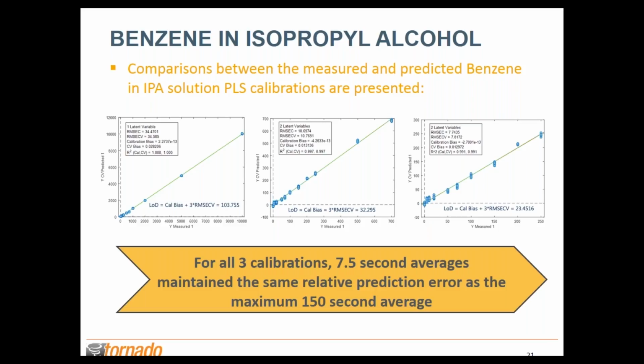Doing so, the full range calibration had an average predictive error of 35 ppm, with the order of magnitude of the limit of detection of around 104 ppm. The reduced range calibration is 750 and below. We improved it down to 11 ppm with a rough 33 ppm limit of detection, and then again you can improve it slightly even further by reducing it down once more to 250 and below and getting a smaller improvement to roughly an 8 ppm average predictive error and resulting 24 ppm limit of detection, based on the cal bias plus 3 times the predictive error.